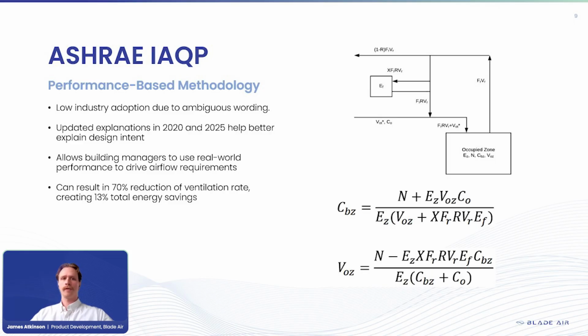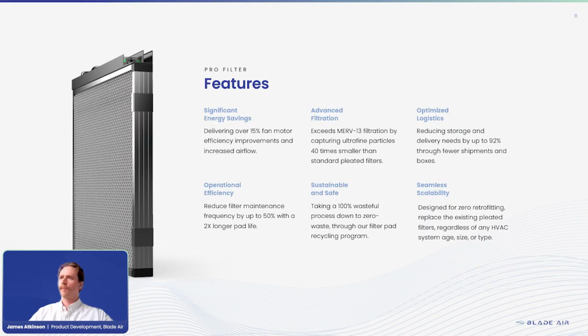So I will take a moment to talk about low pressure filtration. This is Blade Air's Pro Filter. It is an electromagnetic filter that is a plug-in device that uses an electrostatic force to trap dust instead of the mechanical force that you'd see from a MERV 8 to MERV 13 pleated filter. Our filter delivers MERV 13 performance with MERV 8 pressure drop. That is to say, you can reduce your fan energy expenditure because it's not as hard to blow air through the filter, but you're still achieving very high rates of filtration because we use a positive electrostatic force to trap dust in the filter, right?